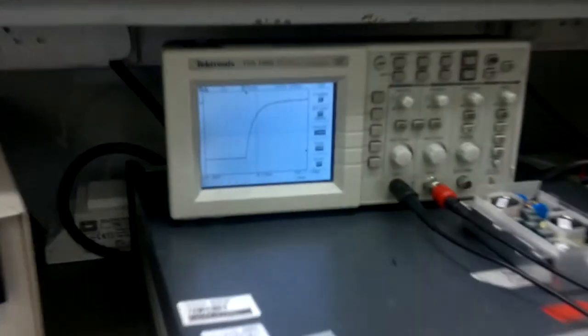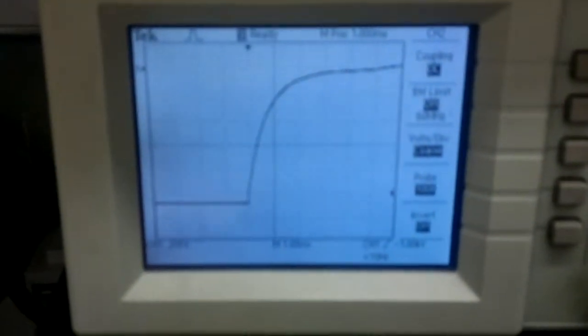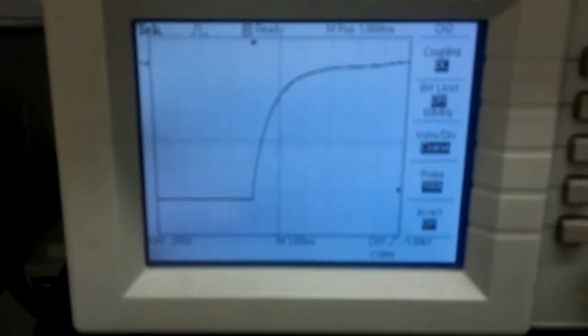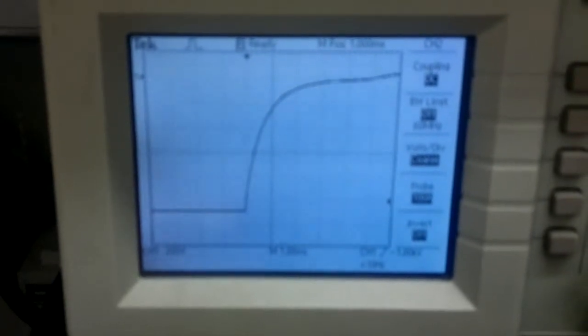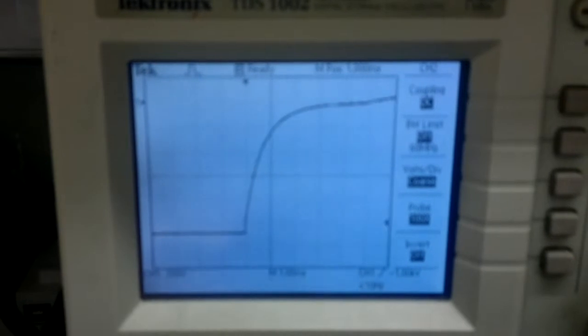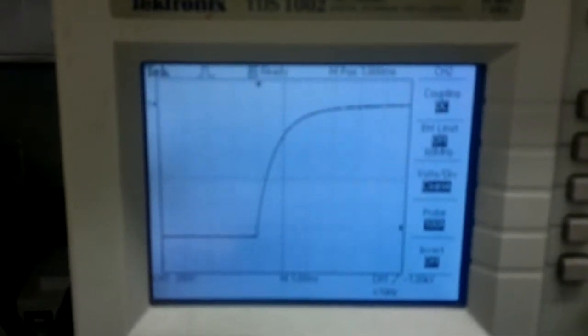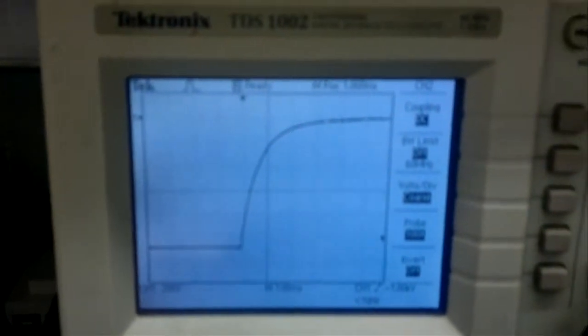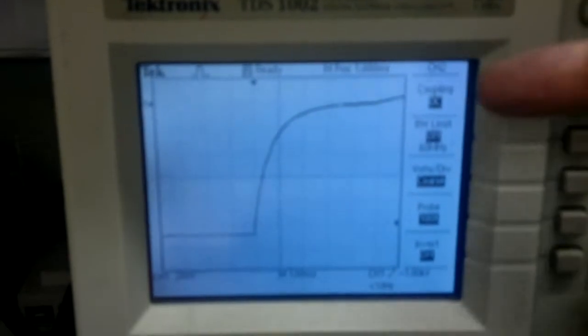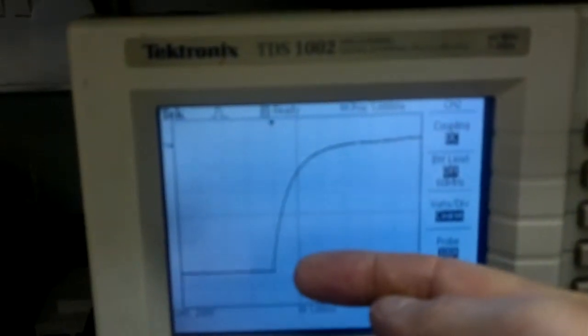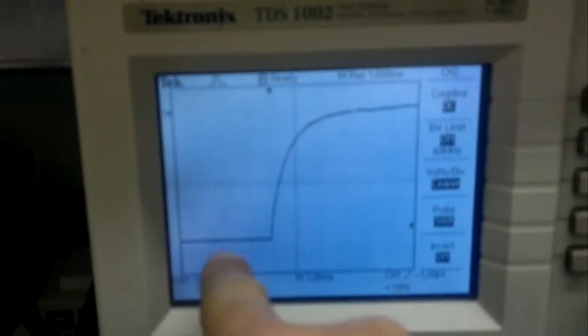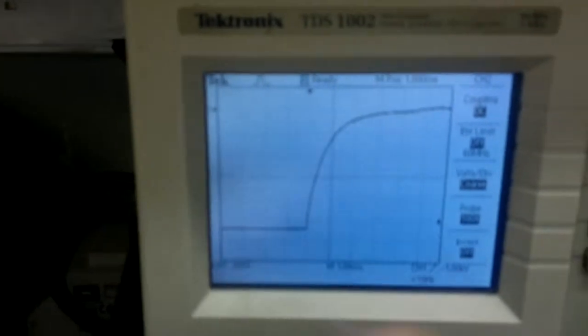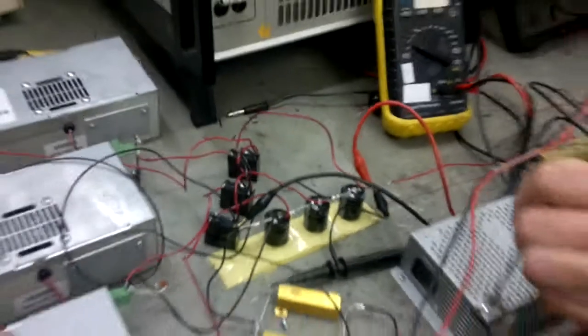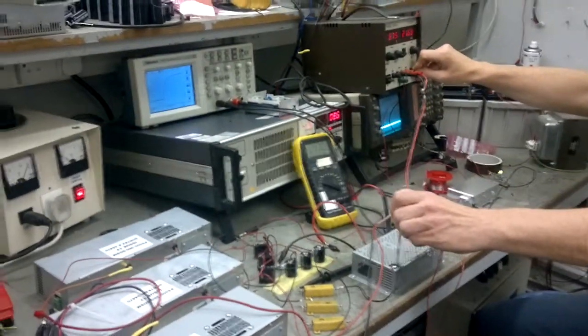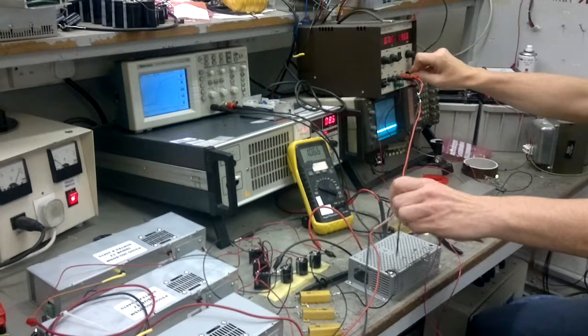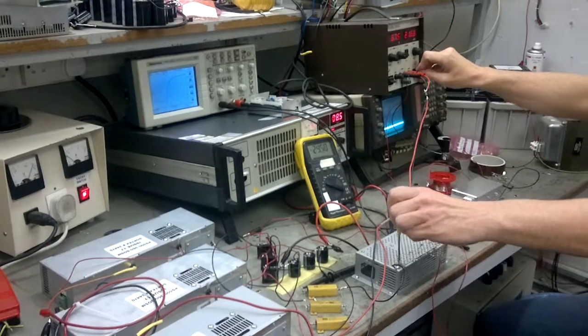and what we'll do now is we'll just look at the storage scope, and what you can see here is that this is 1 millisecond per division, so we can see around 4 milliseconds where the voltage is at minus 1100, and then the voltage pulse recovers. The amplitude is minus 200 volts per division, so here is 0 volts, here is minus 1100 volts, here is around 4 milliseconds which is the time it takes to discharge the capacitors. And here you can see the test being repeated around once every 5 seconds, thereabouts, which is the requirement in the standards.